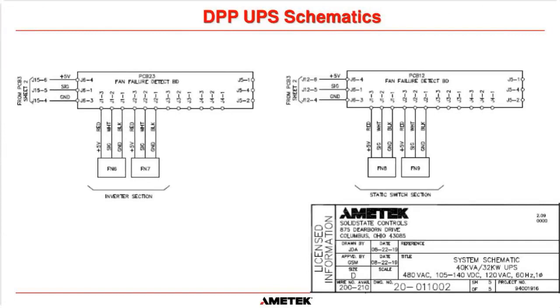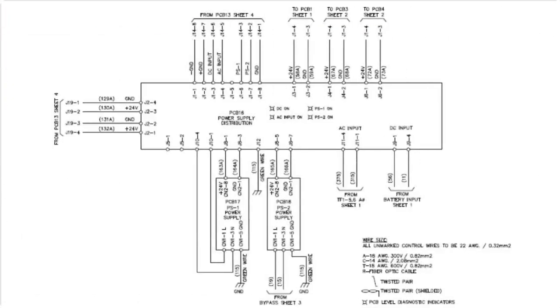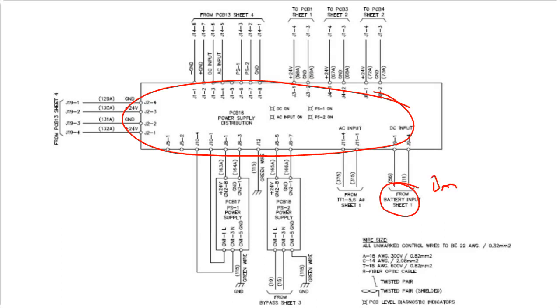And then the last page for this, I think, is the power supplies. Do I go into it in depth? Yep, there it is there. So we use 3 power supplies for the DPP to supply our logic supplies for all of the control boards in this system. One is from the battery. Okay. One is from the AC input, which is the AC input transformer, the 3-phase 480 that gets stepped down on an auxiliary winding on the transformer. And the third one is from the bypass supply.